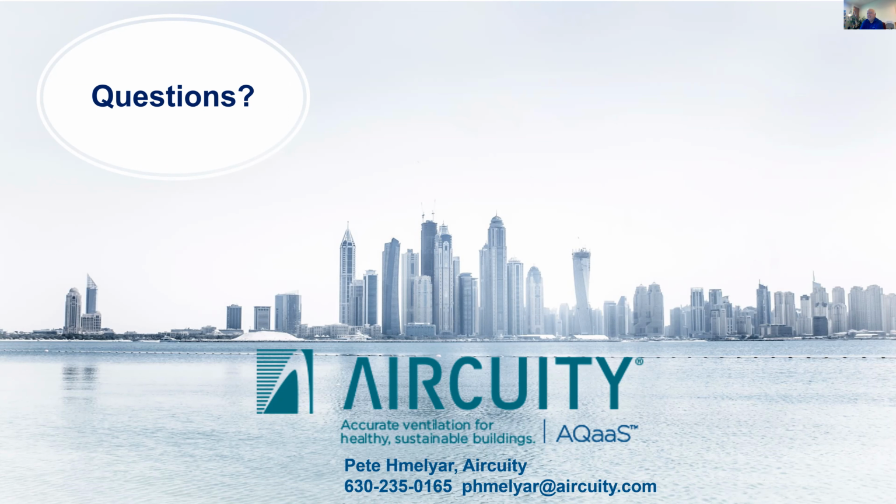Okay, great. Then we've also got a question. What types of air quality parameters are the sensors recording? So what they're looking at is TVOCs, which are total volatile organic compounds. And the T means total, which means we don't know if it's ammonia or hexane or what type of volatile organic it is, but it's the total amount. And there are standards that are set for TVOCs. And that allows the two different types of TVOC sensors to look at literally hundreds of different chemicals, so that when the composite amount of VOCs is above a certain level, the signal is sent to the lab control system, in this case, to increase.